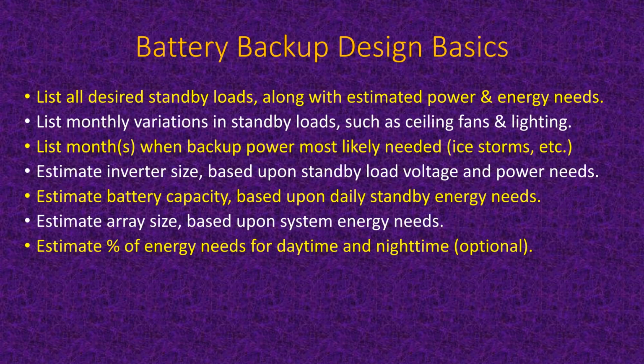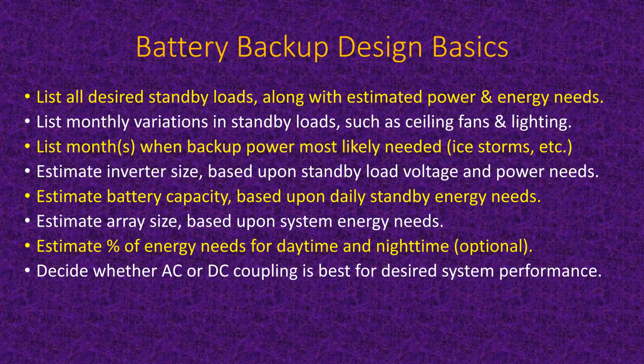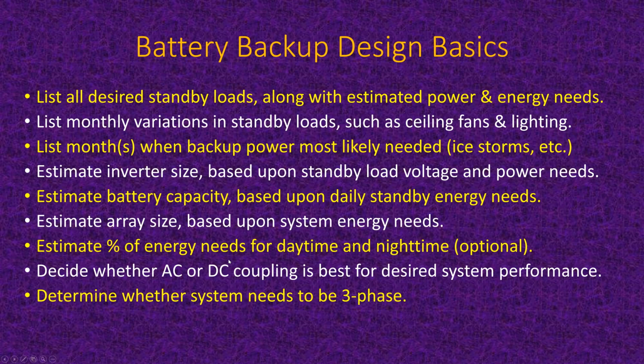It just so happens that the AC coupled systems are really good for cases where you want to use a lot of electricity during the day and not quite as much at night, because then you won't need quite as much storage for night and you'll use a lot of electricity during the day, provided that the sun shines. So there's always a little kicker here that there's always some situations that could change things. Then you have to decide whether AC or DC coupling is best. We just talked about one instance where AC coupling might be best, but there may be others where DC would be better. And sometimes it's a matter of cost. Does it need to be a three-phase system? Not every system out there can be configured for three-phase, so you need to pay attention to that.